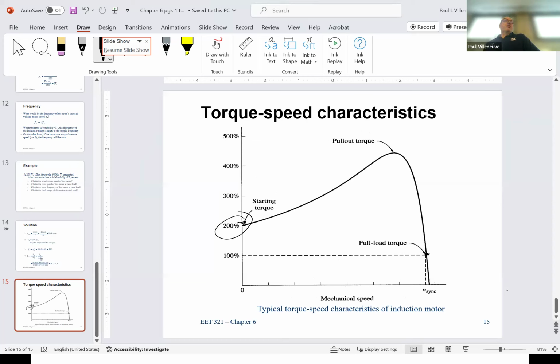The protection on this is you can run this at locked rotor current, which is the highest current it ever has, for an indefinite period of time. Does that make sense? Depends on your perspective, right? You as the electrical engineer are really worried about your electric motor. You're going to burn that thing up, right? Maybe even catch it on fire. But what are the fire people interested in? We want to put the fire out. So they'll keep that motor running as long as possible because it becomes a life safety issue.